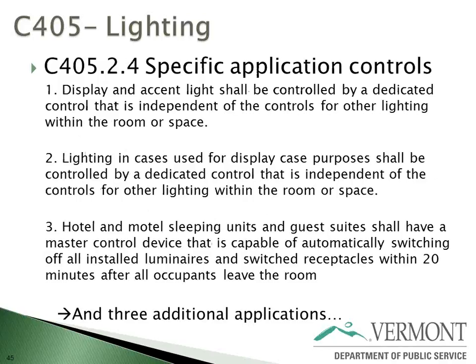Beyond the general lighting control section, there are specific applications that don't fall under any other category. This is verbatim language from the code: display cases, display and accent lighting. The third one stands out most—hotel and motel sleeping units and guest suites now have to have a master control device so everything can be switched off within 20 minutes after the occupants leave the room.